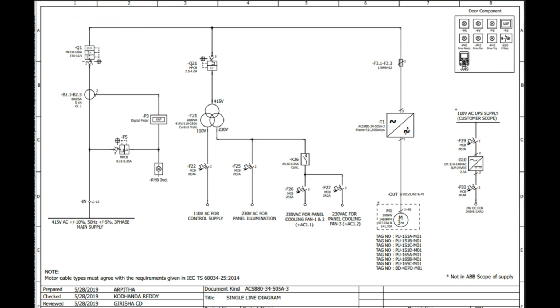The first tapping you can see here is for MPCB and the rating is given for all these switchgears. For this it is 0.16 to 0.25 amps and this is for RYB indication. Once you switch on this MPCB you can see whether the main supply is there or not. Next, if you go ahead, there is one more tapping for the VAF digital meter, that is voltage, ampere and frequency. Further you have to go ahead with Q1, that is MCCB.